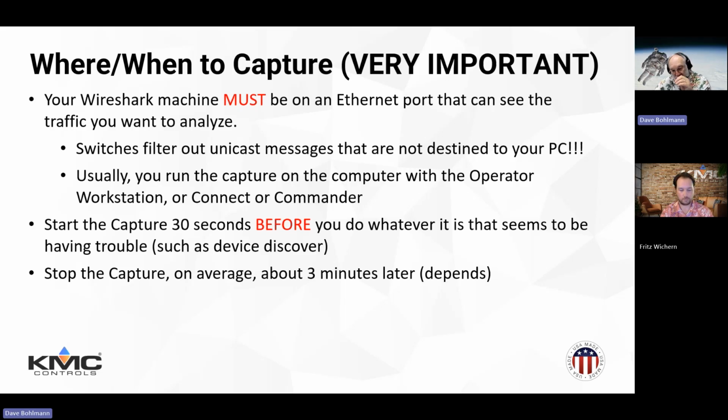Okay, and we'll go a little bit more into detail about that here in a little bit. And like I said before, it's very important to know where and when to do your capture. And again, because of Ethernet switches, if you plug your PC into the same Ethernet switch as, let's say, Niagara or whatever, the switch is going to filter out any messages that are what we call unicast messages that are not for your PC.